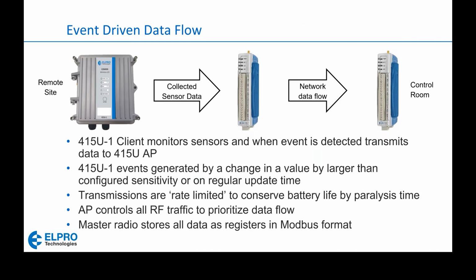Okay. Now, what we do is most of the time, the traffic is event driven. So what we do is we monitor the 4 to 20 milliamp inputs. So the radio will wake up. Let's say, for example, it wakes up every 10 minutes. It powers on the 4 to 20 milliamp loop. It looks to see if there has been a change since the last time it was powered on. If the 4 to 20 milliamp signal going into this remote radio system has not changed, then the radio does not transmit anything. Then we have just our default update times, and these function as more of a communications check or just a confirmation so that the SCADA system in the control room knows that this remote site is still alive and still has power. So we set our update times maybe once per hour, once every 2 hours, something like that, making sure we don't consume too much power and have to get a really big solar panel or that sort of thing on the radio system.